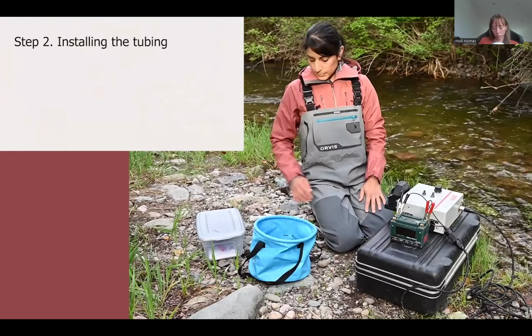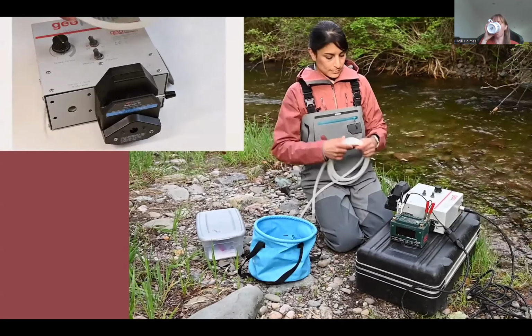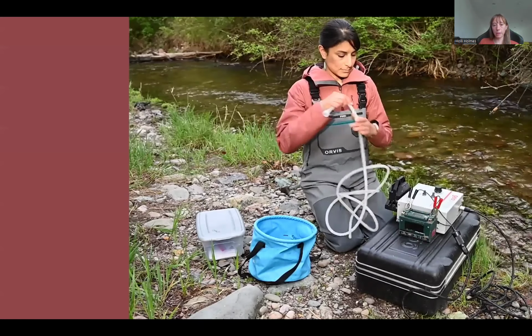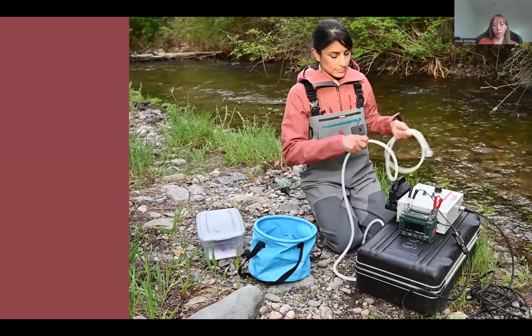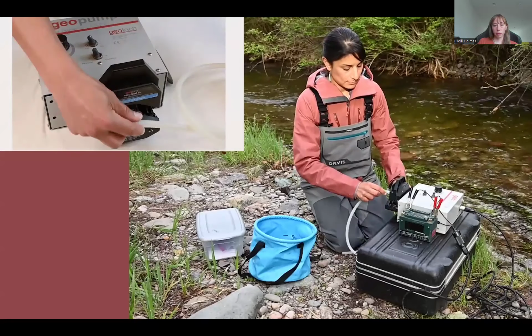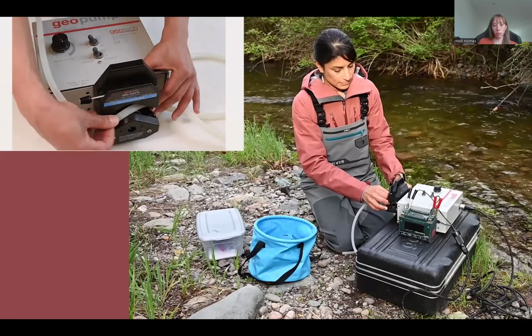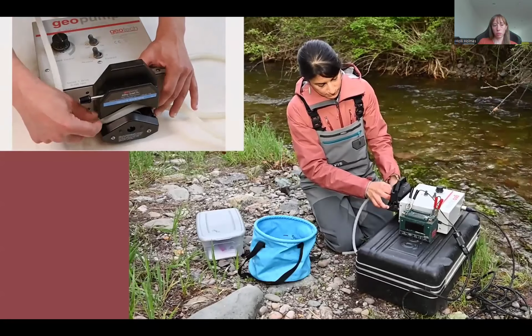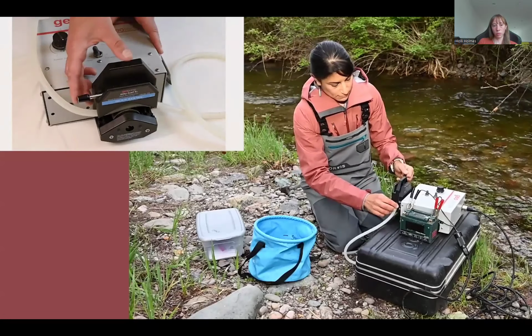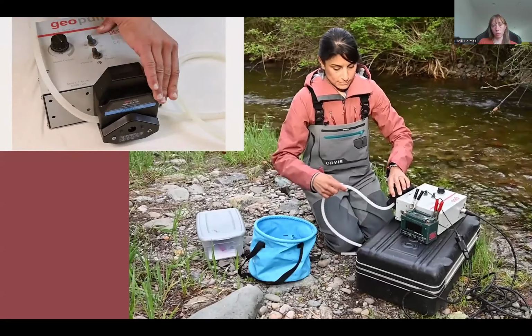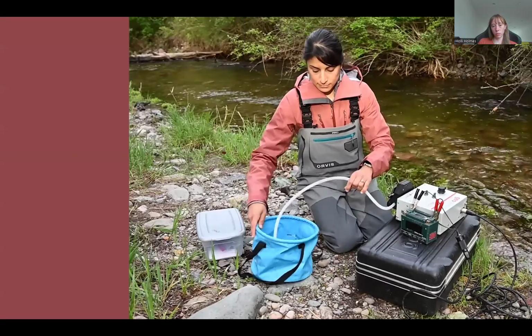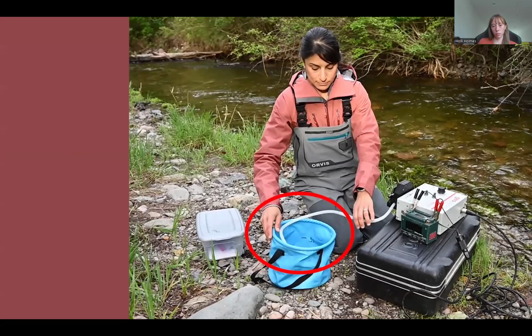Step 2, installing the tubing. Pull the lever in the pump head to open it. Align the tubing and load the tubing into the pump head. Push the lever to close the pump head and ensure that the tubing is not being pinched along the edges. Place the outflow end of the tubing into the outflow bucket. You may find it helpful to secure the tubing to the side of the bucket, as the tubing may flop or jiggle when the pump motor is running.